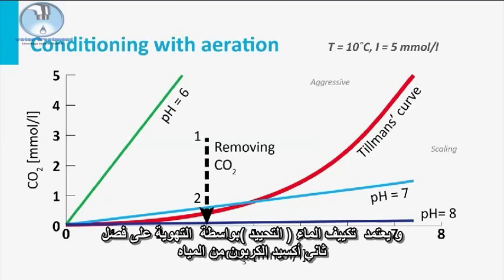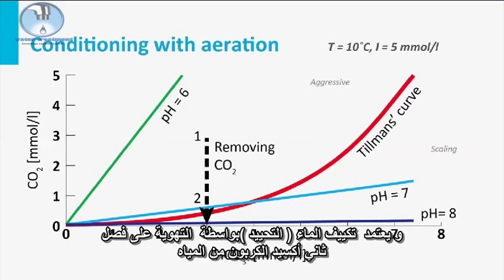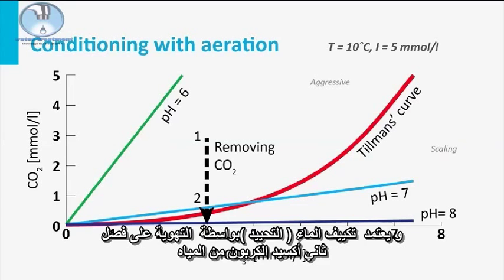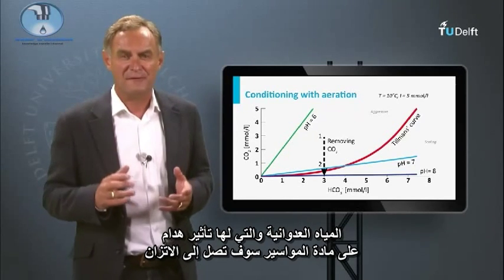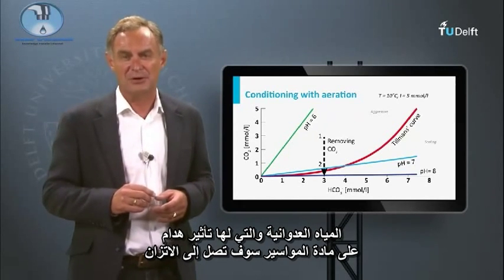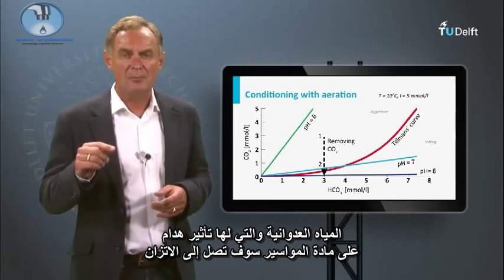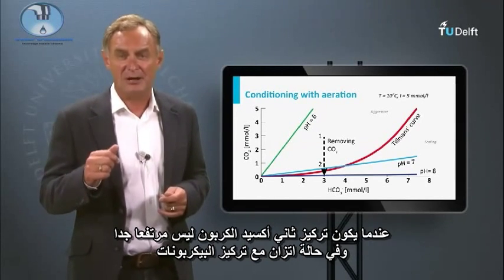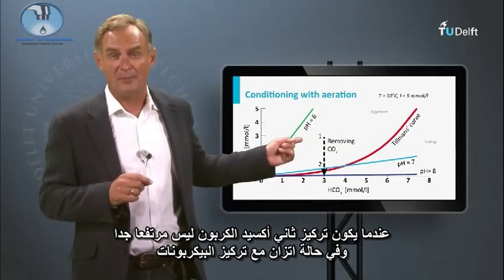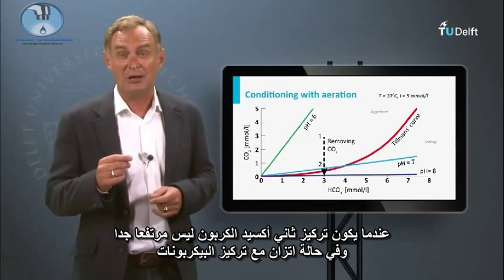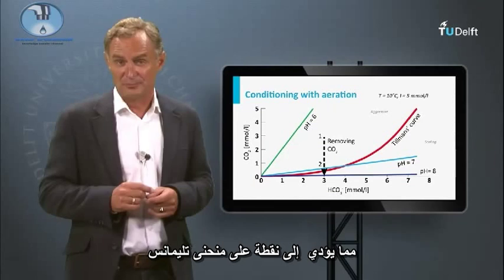Conditioning with aeration is based on stripping carbon dioxide out of the water. To see the effect of stripping on water composition, the so-called Tillman's Curve is used. Aggressive water that has a corrosive effect on pipe material will reach equilibrium when the concentration of carbon dioxide is in equilibrium with the bicarbonate concentration, resulting in a point on Tillman's Curve.